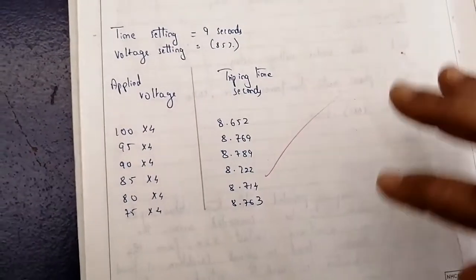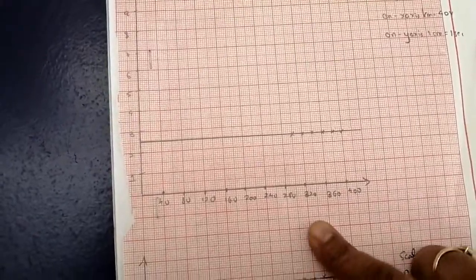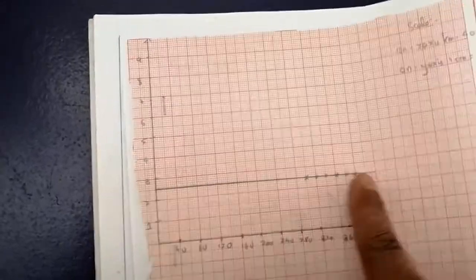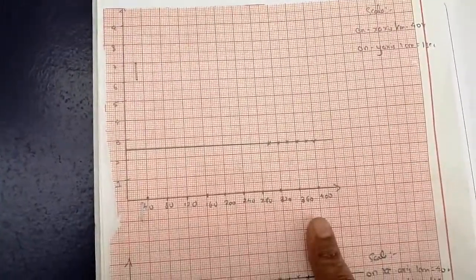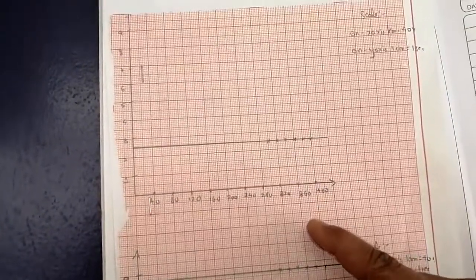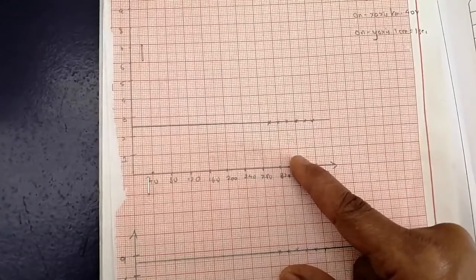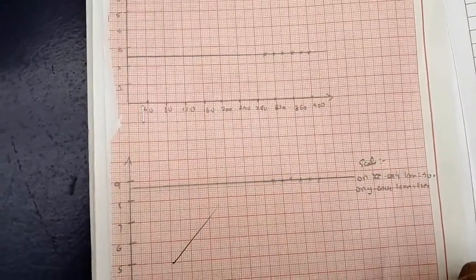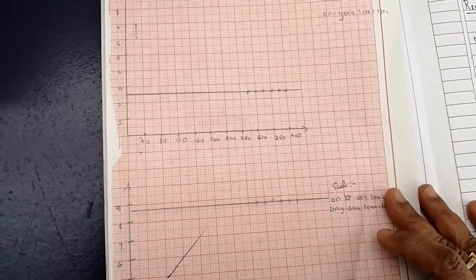Now let us look at the model graph. You can observe the model graph with two axes: the X-axis is the applied voltage and the Y-axis is the time taken. The graph is almost a straight horizontal line — almost constant. This indicates that whatever is the value of the fault voltage, the time taken by the relay is almost constant. We have satisfied our aim — we have plotted the DMT characteristics of the solid state relay, tabulated the values, and observed that the characteristic is almost constant. This concludes the experiment of the solid state under voltage relay.